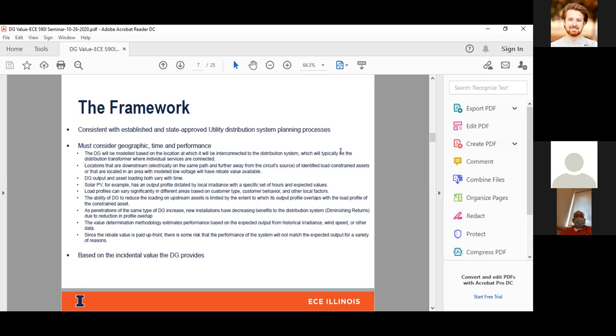I'll give an example. The utility would go through what we call a load forecasting and a load analysis process. You take a look at a feeder, for example, you look at the substation, you forecast over the next 5 years what its loading is going to be, and then you compare that to the capacity of the transformer. And if you're under normal operating limits in 5 years, then you're good. You don't really need to do anything with that asset. However, if you're above the normal operating limits and you might overload that transformer, then you would look at putting a project together to upgrade that transformer. So this is an example of how utilities invest based on a specific planning process, and that drives really how utilities today operate. So staying consistent with that, and given the fact that this has been approved already by the local jurisdiction, was a key philosophy here. The second one is trying to abide by the law, which is making sure that the framework meets the geographic, time and performance parameters that were put in it.